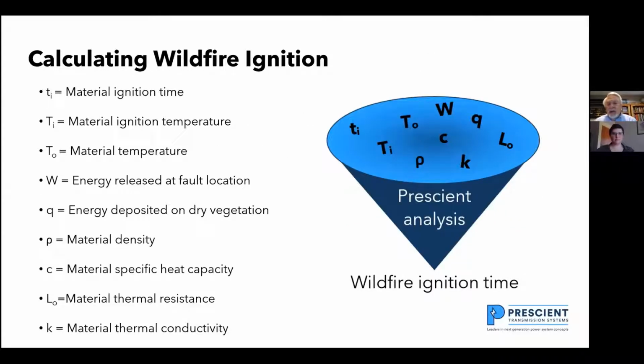When I'm looking at calculating wildfires, there's a whole bunch of items I have to consider. First is the material ignition time. And if I can clear faults before materials ignite, then I won't start wildfires. I want to know the material ignition temperature. Typically, the material ignition temperature is around 450 degrees Fahrenheit. The material temperature is going to start out at ambient temperature plus solar radiation. So the material may start out at 120 degrees Fahrenheit.